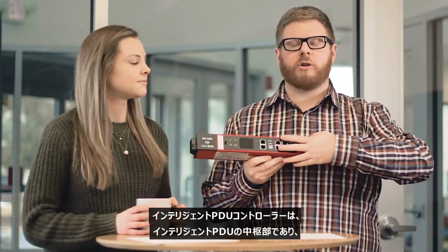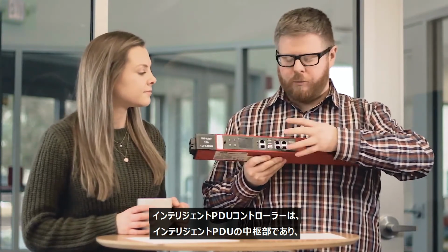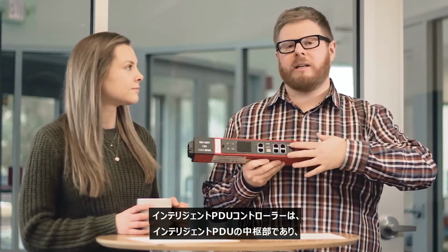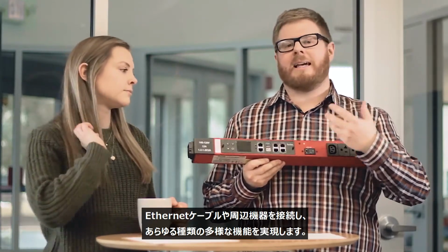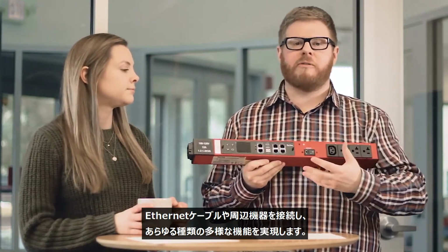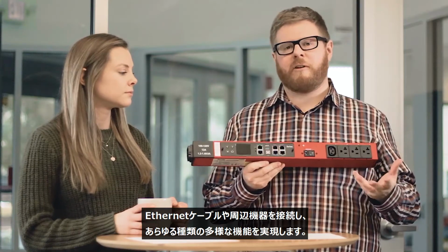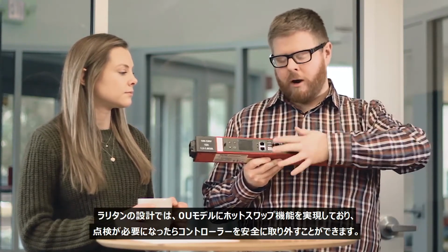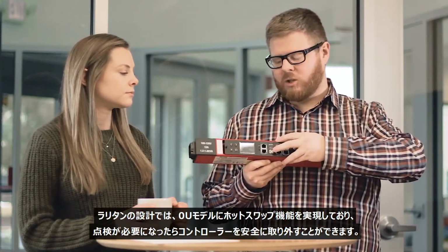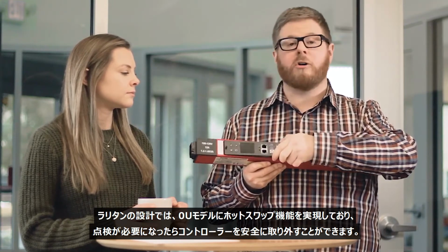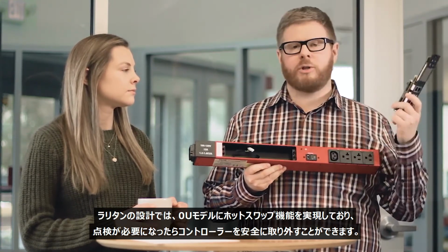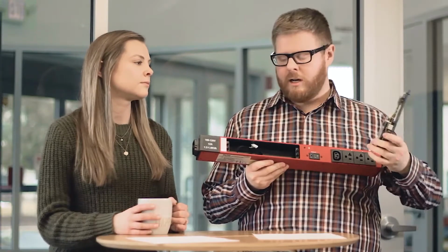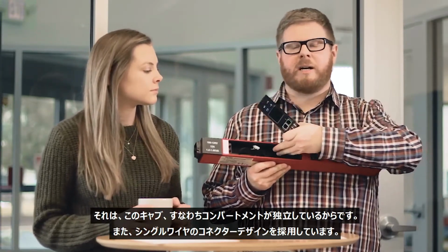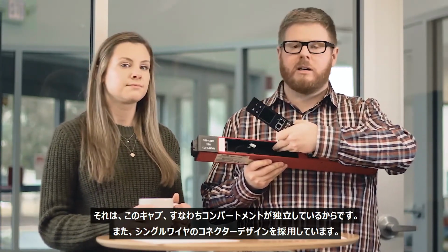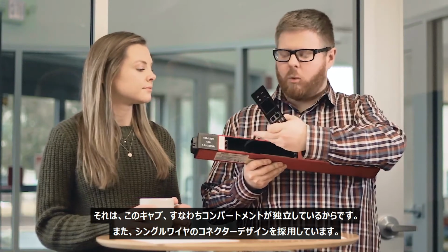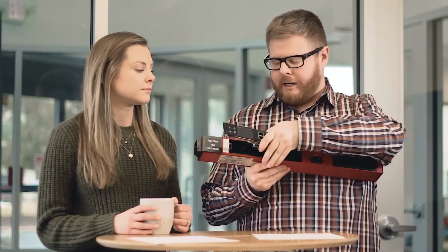An intelligent PDU controller really is the brain of the intelligent PDU, and it allows you to connect things like Ethernet cables and peripheral devices to enable all types of different functionality. On our design, we have a hot swappable capability on our 0U models, which allow you to remove the controller if you need to service it, and you can do it in a way that's safe because the compartment is isolated, and we have a single wire connector design.